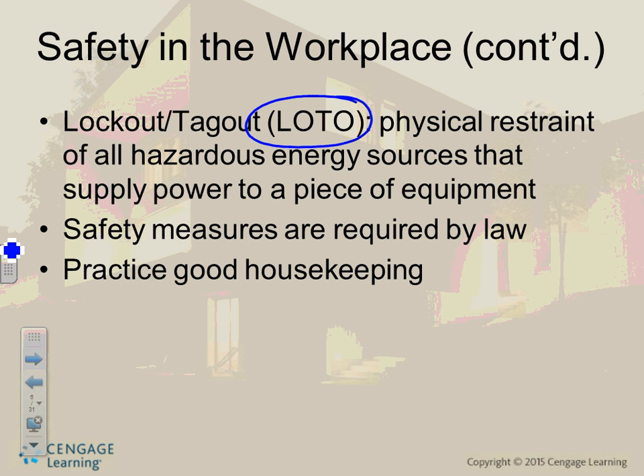So these are the only exceptions, guys, that you can work energized: if you introduce more hazard by shutting it down, like hospitals, or if you cannot troubleshoot the system without it being energized. You get into an air handling unit, you need to troubleshoot it. You can't troubleshoot it without it energized, so you have to energize it and work on it energized. So other than that, you lock it, you tag it, and it is the law.